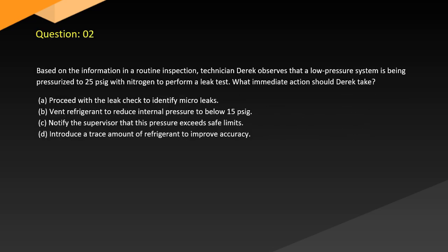Question 2. Based on the information in a routine inspection, technician Derek observes that a low-pressure system is being pressurized to 25 psig with nitrogen to perform a leak test. What immediate action should Derek take? A. Proceed with the leak check to identify micro-leaks. B. Vent refrigerant to reduce internal pressure to below 15 psig. C. Notify the supervisor that this pressure exceeds safe limits. D. Introduce a trace amount of refrigerant to improve accuracy.